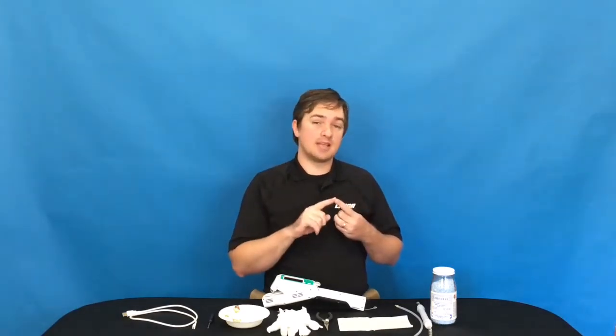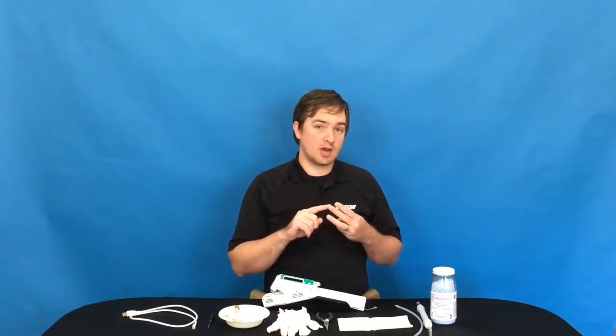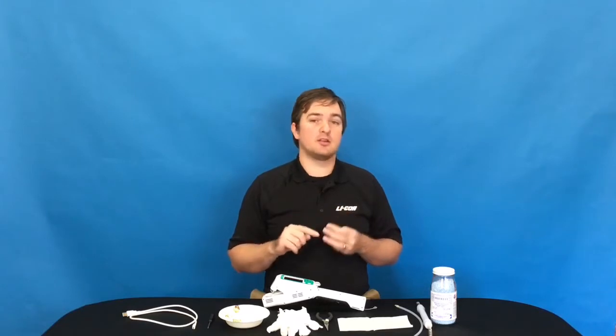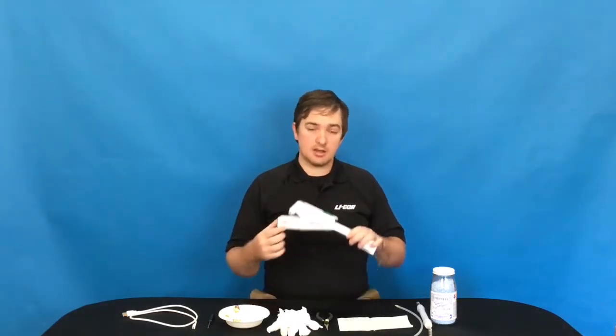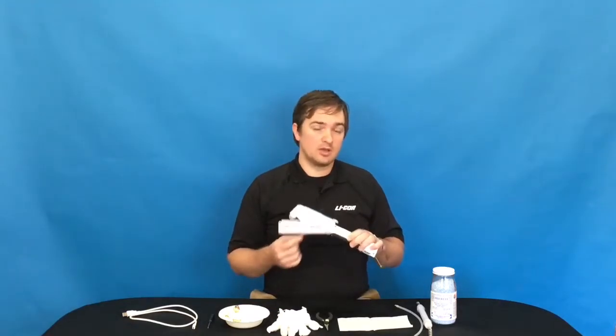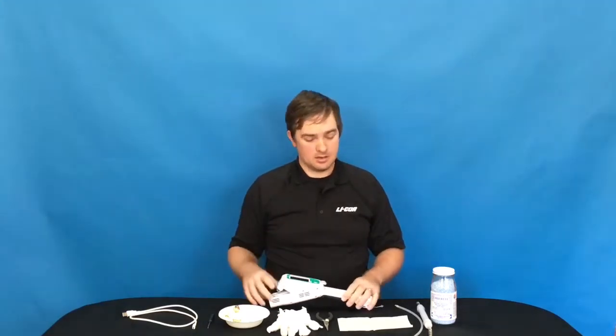One would be using desiccant with an external pump. Another would be using a tank of dry air. Both of those methods are described in a separate video. The third method is using the LI-600's internal pump to flow air from a desiccant into the relative humidity sensors.